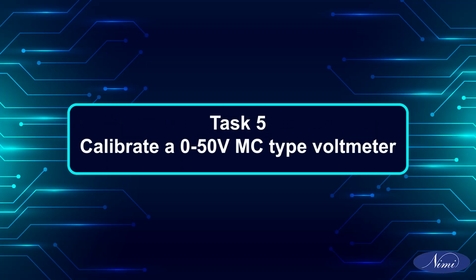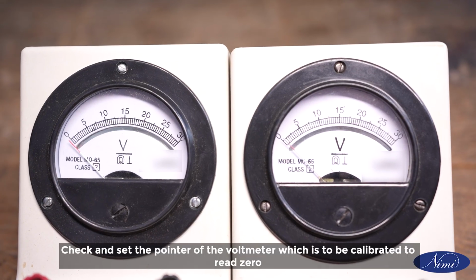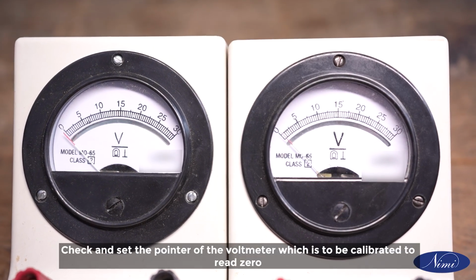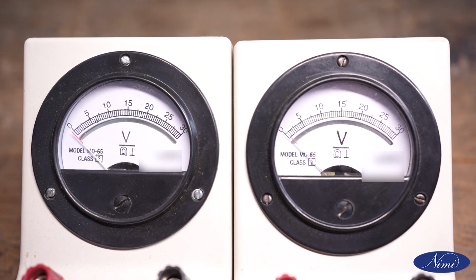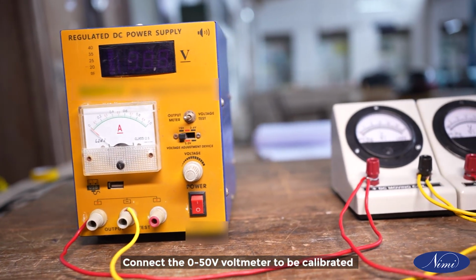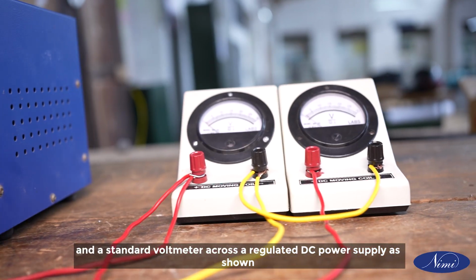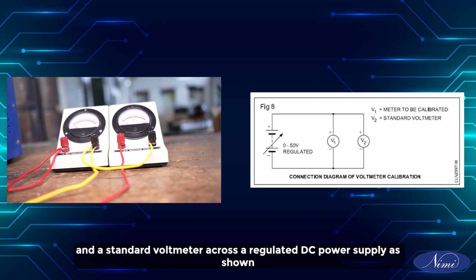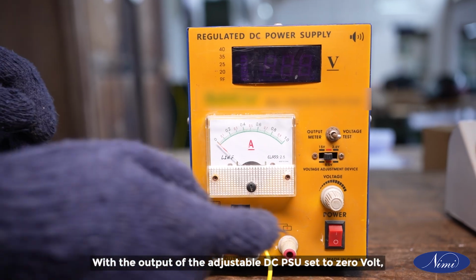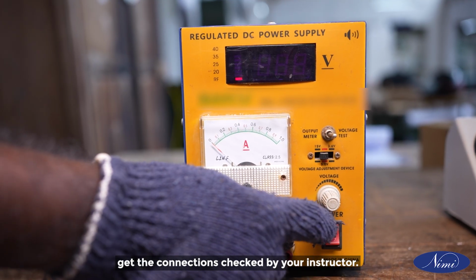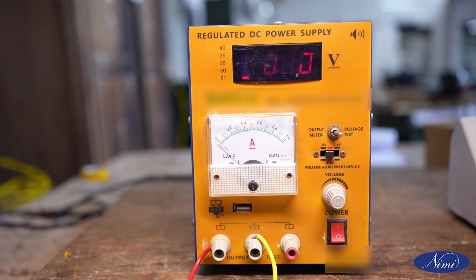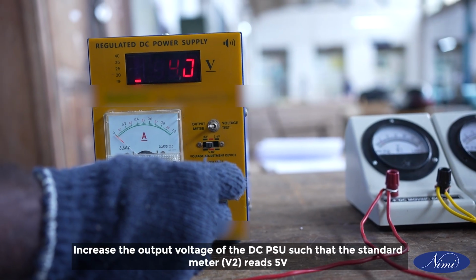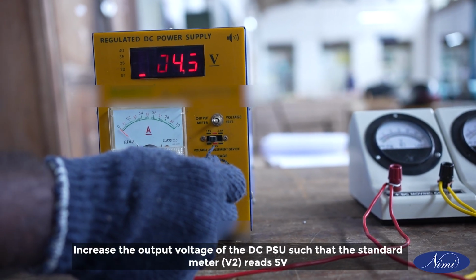Task 5. Calibrate a 0 to 50 volts MC-type voltmeter. Check and set the pointer of the voltmeter, which is to be calibrated, to read 0. Connect the 0 to 50 volt voltmeter to be calibrated and a standard voltmeter across a regulated DC power supply as shown. With the output of the adjustable DC power supply unit set to 0 volt, get the connections checked by your instructor. Increase the output voltage of the DC PSU such that the standard meter, V2, reads 5V.